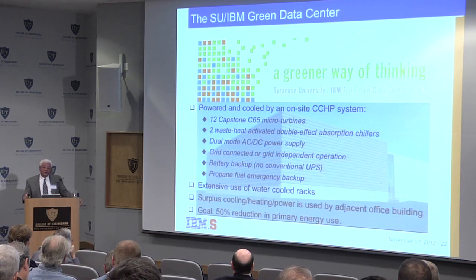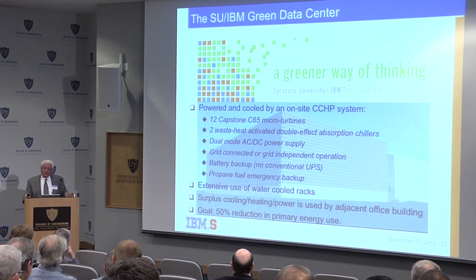Okay, we have battery backup. There's no conventional UPS. The turbines provide that function, and we have a room full of batteries. Some of the weight of those batteries would have been residing in the bottom of the turbine anyhow. So we have 44 tons of batteries that can run that data center at full power, at 500 kilowatts, for 22 minutes. It has the propane fuel emergency tank that we can run on for a couple of days, in case somebody punctured the gas line. That will be our biggest risk.